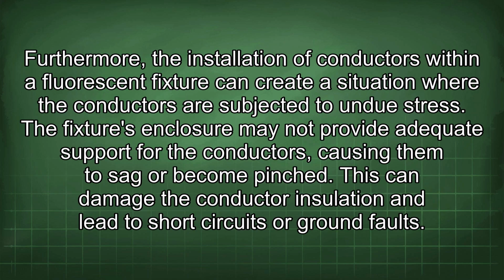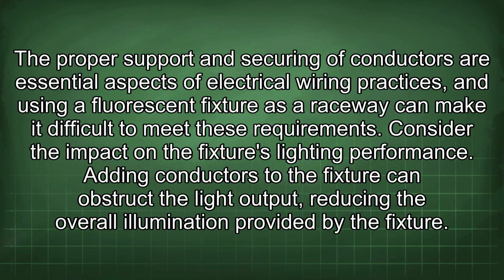Furthermore, the installation of conductors within a fluorescent fixture can create a situation where the conductors are subjected to undue stress. The fixture's enclosure may not provide adequate support for the conductors, causing them to sag or become pinched. This can damage the conductor insulation and lead to short circuits or ground faults. The proper support and securing of conductors are essential aspects of electrical wiring practices, and using a fluorescent fixture as a raceway can make it difficult to meet these requirements.